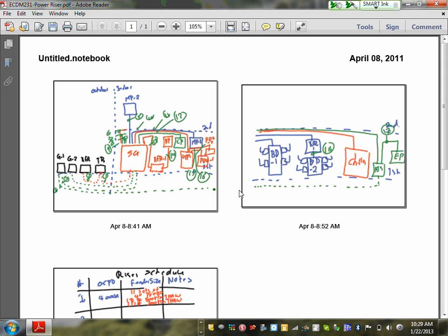So now, all of a sudden, utility power comes back on. The system recognizes there's utility power. Now there's two options. Are we doing an open transition or a closed transition transfer? Okay, so we're doing a closed transition. So at that point, the utility breaker is looking at the generators, kind of like Gen 1 and Gen 2 were, and waiting until everybody's in sync on that waveform, and then we'll close the utility breaker in, and once the utility breaker is on, then we will start dropping off the generator so that there's not a bump. There's always a bump going to the generators because you lost power.